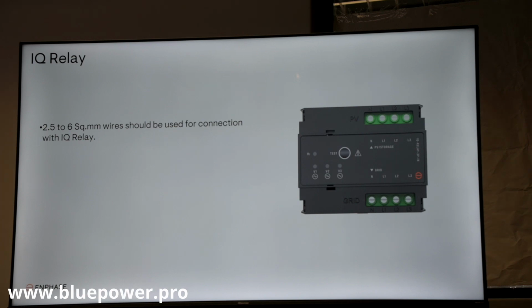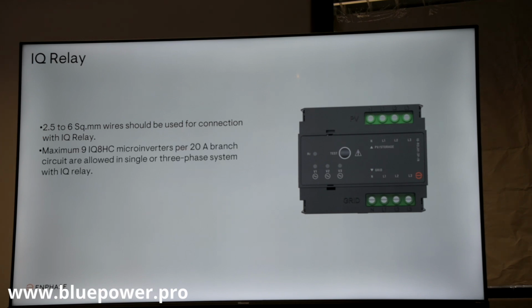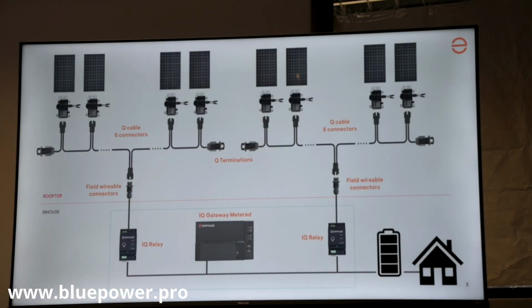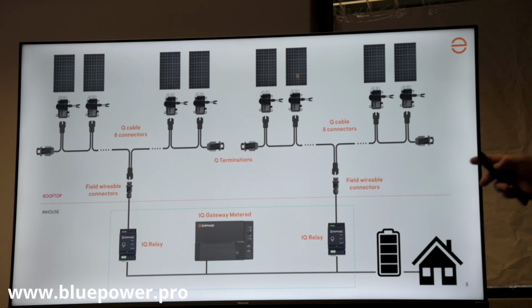Now, when you connect these, you can use anything from 2.5 millimeter square to 6 mil square. We normally use 6 mil for the connection from the relay up to your DB, etc. I've spoken about that. So this is basically how a normal setup works. Let's say you've got, in this case, 8 connectors. So let's say you've got 16 panels, so you'll need 16 microinverters. So 8 on a single phase line. For each branch, you will have a relay, and then those relays will connect in parallel. Of course, your microinverters on the branch circuit are also connected in parallel.